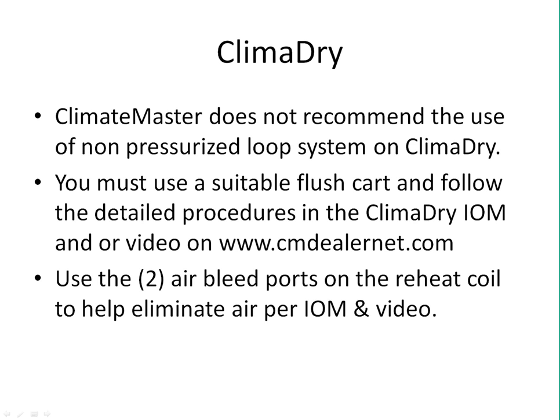In other words, you're almost deadheading your flush cart, creating a lot of pressure with the modulating valve directing all the flow up into that reheat coil. Guys miss that, and boy, if you have an airbound reheat coil, you're going to have complaints because it can't do what it's supposed to do, so it's over air conditioning the home. Typically not very comfortable. It's not only cold, but now it's clammy because you're not pulling enough moisture out of the air. Again, depending upon your project location.